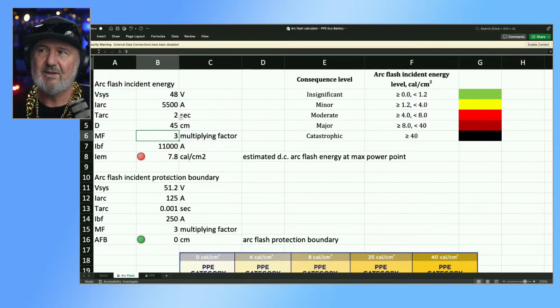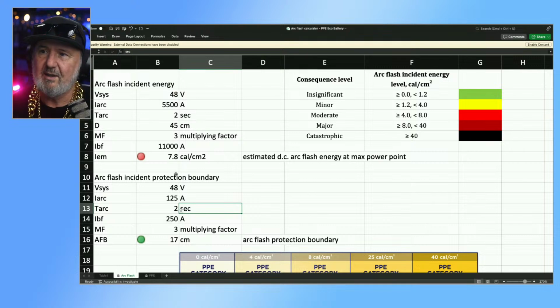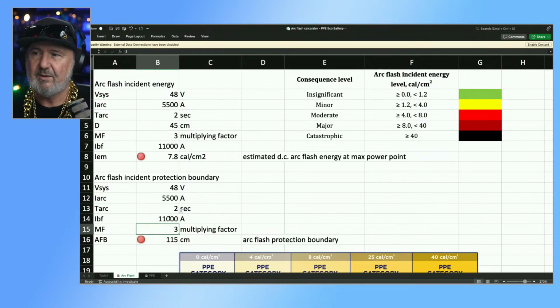Now, the second part to this calculation is the incident energy boundary. So the arc flash incident boundary is the zone to which PPE is required. So let's fill this one out, 48 volts. Arcing time is 2 seconds. Bolted fault current is 11,000 amps. And we've got 1.15 metres. So for those who are imperial, it's probably about 4 and a bit feet, I'd say. So within that sort of zone, you need to have PPE, and the PPE requirements are listed below.